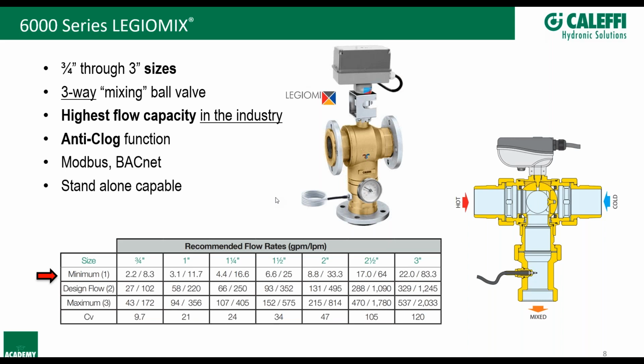Not really. I mean, the valve is operated by the control. The control is looking at the sensors. You can see it here, the mixed outlet sensor right here in the body of the valve. Those are 10K ohm sensors. Really, the only issues I've seen so far where a valve is a little bit out of whack is because of loose wiring connections or a cut wire, for example, where it will show an open or a short on the control, but there's really no calibrations necessary, no.